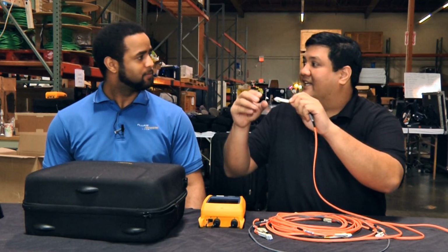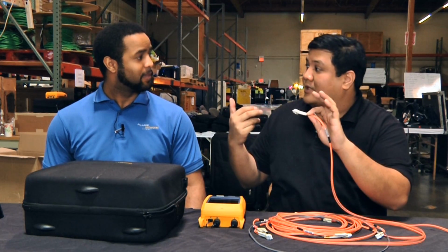Right. So what that's the study of is what happens to light as it transmits down a fiber optic cable. It's following a physical phenomenon where you're transmitting a pulse of energy, and so it actually is transmitted as a wave. And when it reflects back to you, you can tell a number of different things have occurred on the channel just by analyzing carefully what you see and when you sent it. Now, one of the important things to realize about OTDR and any equipment that uses the phenomenon is that the same side that is sending the light is also going to be receiving the light back.